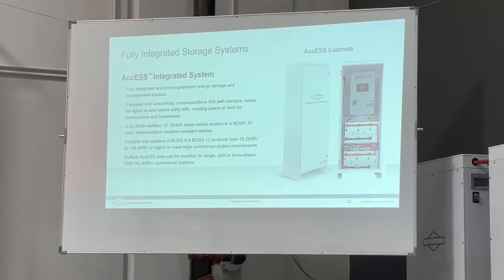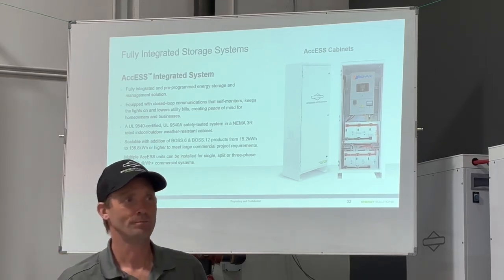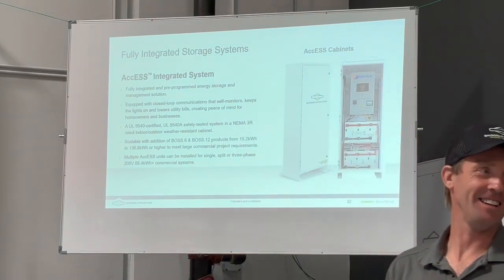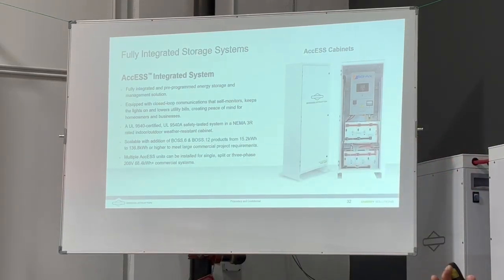Maybe we do come out with a cabinet for the 15K. Right now we've kind of come out with a battery for the 15K, and we'll see about that. Maybe we just start selling more of the louvers with gaskets. What we need is bigger fans and a slightly bigger cabinet to accommodate the Sol-Ark 15K. The other limitation on these cabinets is, if you do an AccESS cabinet, you're looking at 23 kilowatt hours of storage for a 15K inverter, which is capable of burning through it in a couple hours, so it's not quite enough storage. Ideally we could fit 8 batteries in a 15K cabinet.